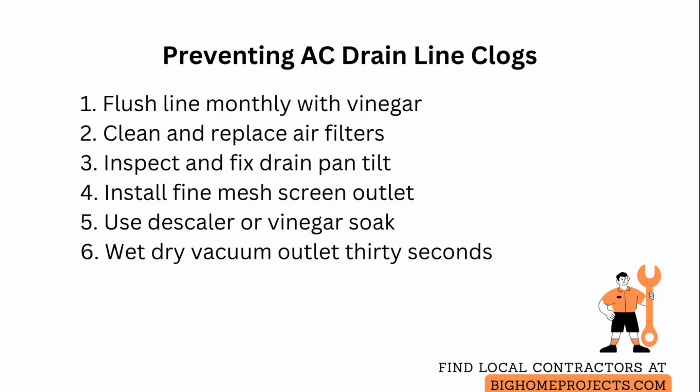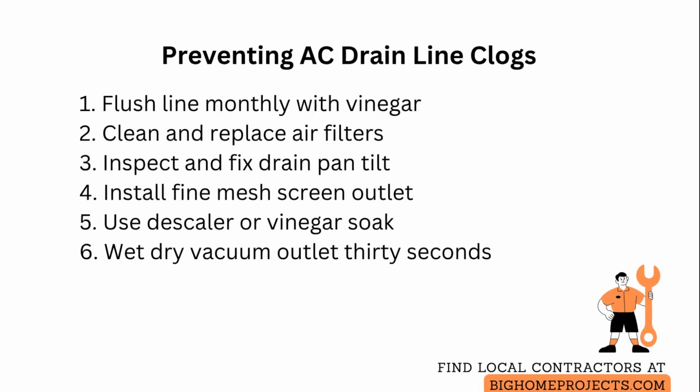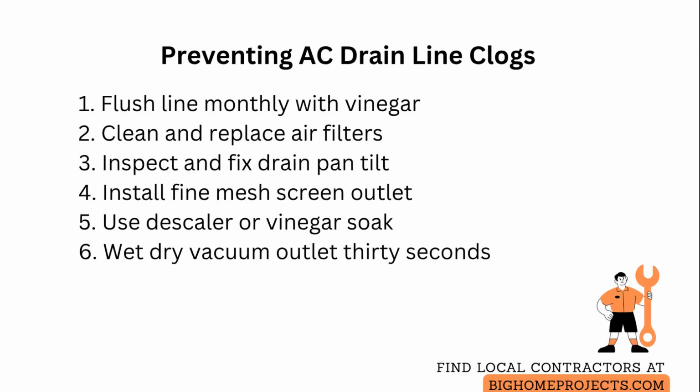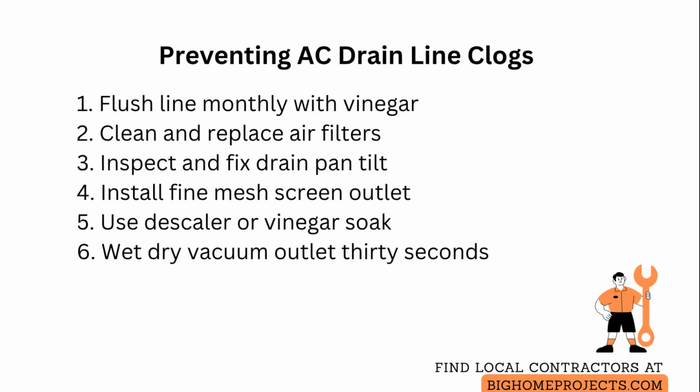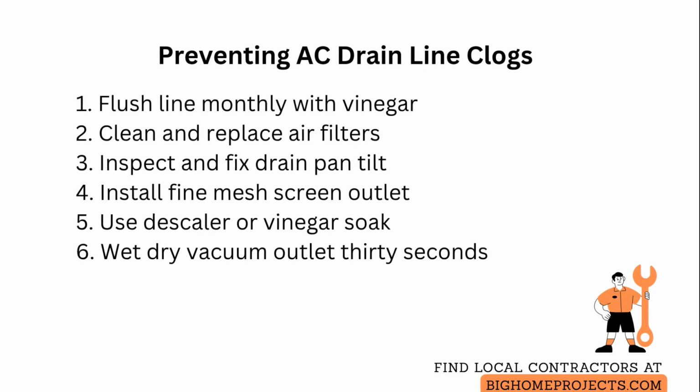Insects and small animal remains can plug traps and elbows, so install a fine mesh screen over the condensate outlet and check under the outdoor unit where critters nest. Mineral scale from hard water will harden inside plastic tubing. Periodically run a descaler or a vinegar soak for 10 minutes and then flush thoroughly to restore flow.